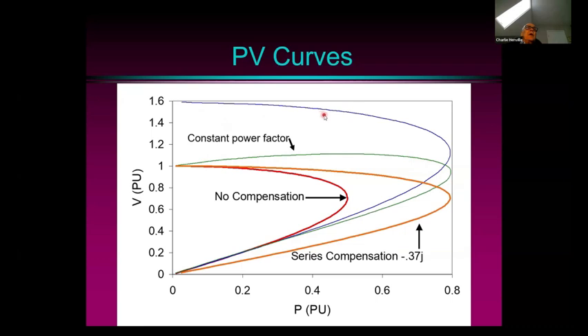So this one is with no compensation at all. This is with constant power factor. And this is another way of increasing the power delivery by adding a series compensation, which is actually decreasing the magnitude of X. So there are various ways to increase the amount of power you can deliver without doing anything about increasing the amount of transmission capacity, which is what a lot of people would like to do.